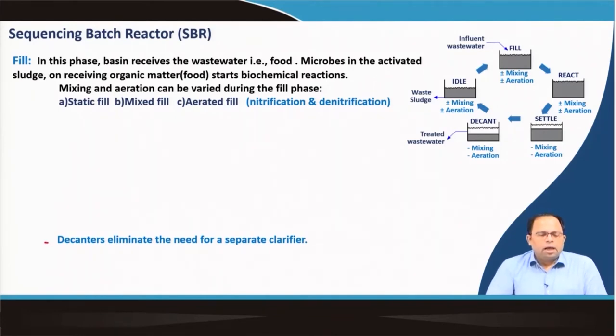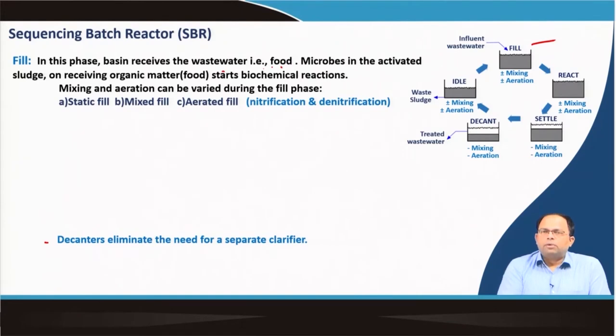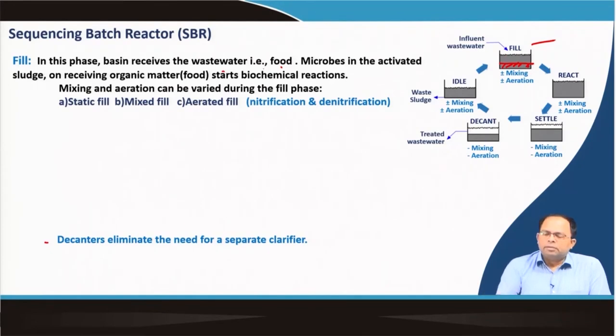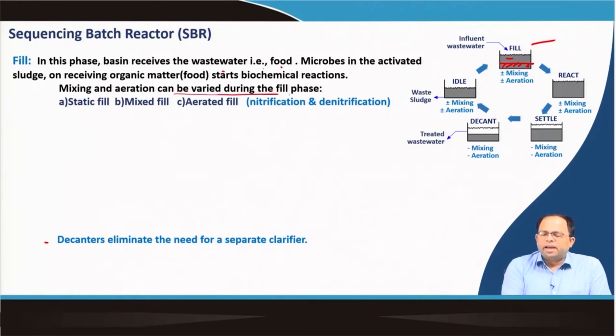In the fill stage of the sequencing batch reactor, the basin receives the wastewater — which is food for the microbes already present in the activated sludge in the chamber. Some amount of sludge is already there, and as soon as the wastewater comes in, the microbes treat the organic matter as food, start consuming it and growing, while the organic matter in the wastewater gradually reduces. Mixing and aeration can be varied during the fill phase: we can have an aerated fill, a mix fill, or a static fill.